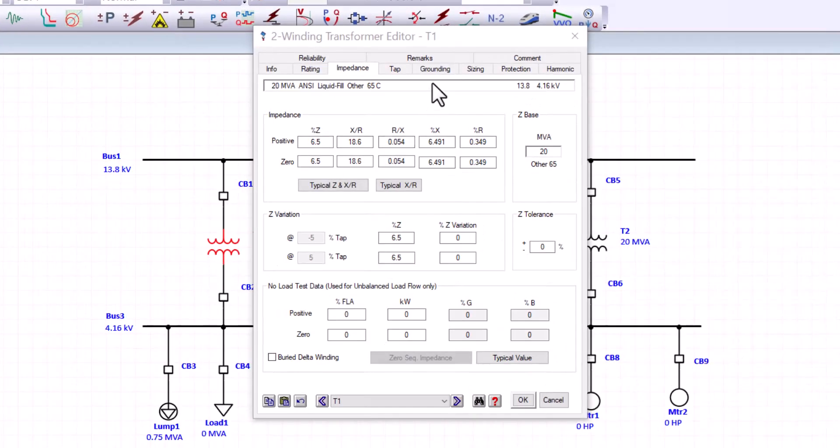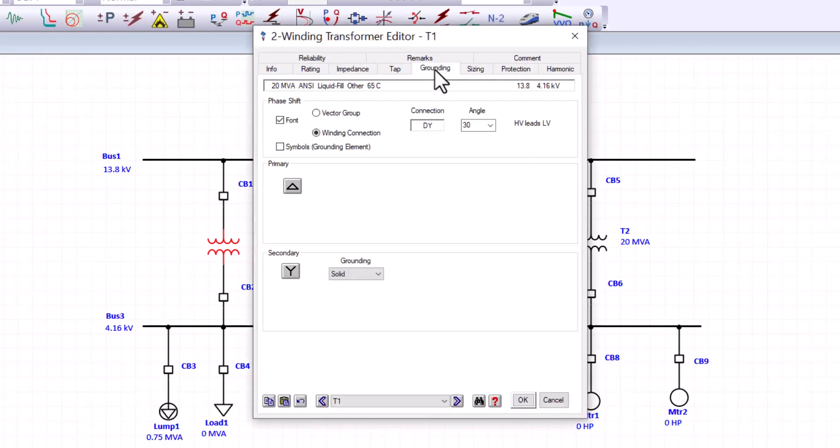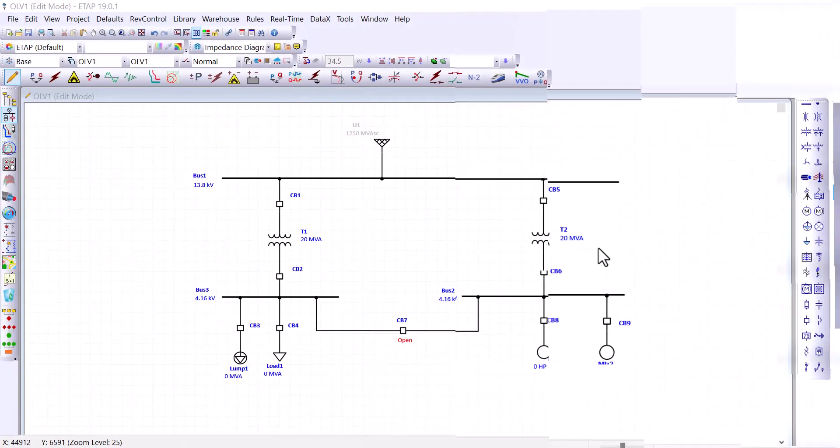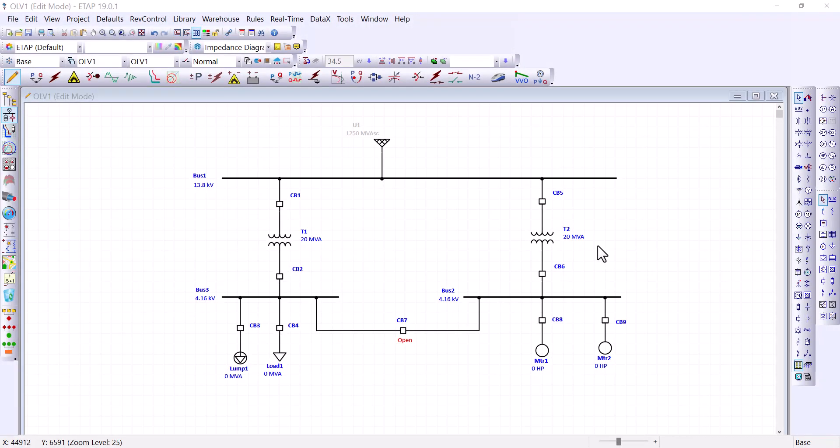Next, we can talk about the transformer winding. And if you go to the grounding tab, you can see that the primary side of this transformer is connected as delta. And the secondary side for that transformer is connected as Y. And the Y connection has a solid grounding. Okay, so to expedite the process a little bit, I would like to point out that T1 and T2 are identical. So you can enter the same nameplate ratings that we did for T1 into T2.